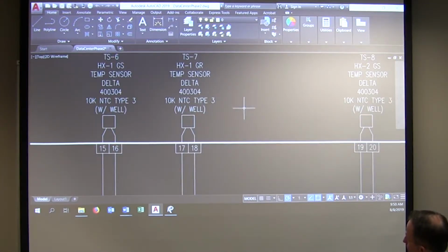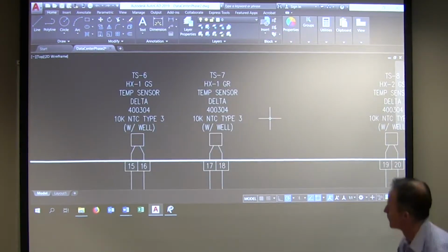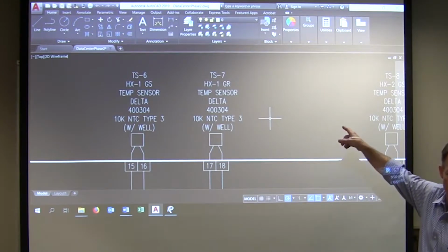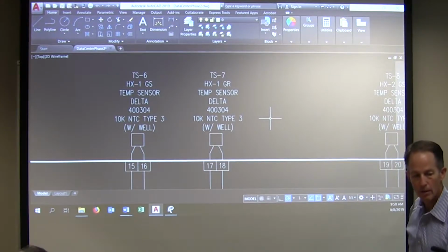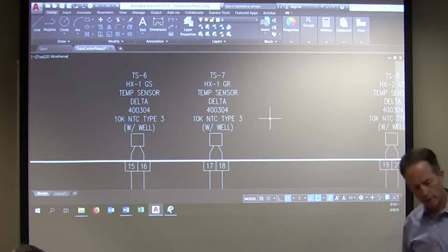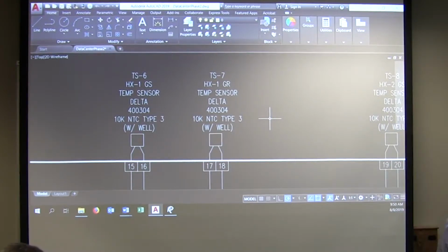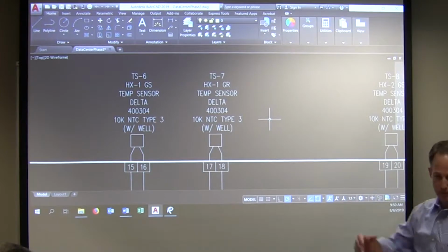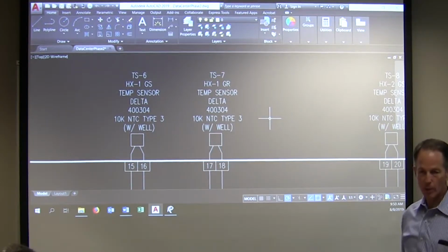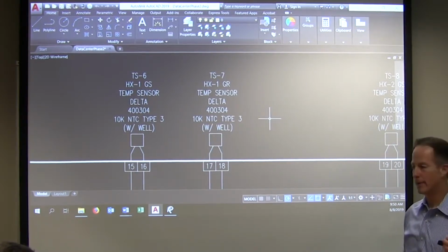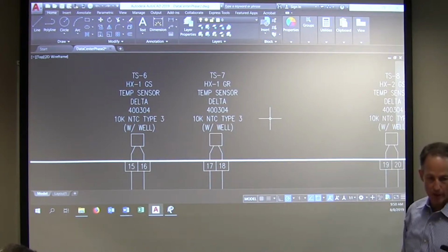A lot of times we get something like this, right? If I can get it to the right level, there we go. Does this look familiar, Brett? How come it doesn't have a decimal through that period, just because it's a tighter range? Oh, down below 90 degrees, less than 10,000. Yeah, I think once you get to a point where they can show a decimal... but really when we're talking a tenth of an ohm, I don't even know why they put it on here. That's such a small change, it's really not going to matter.